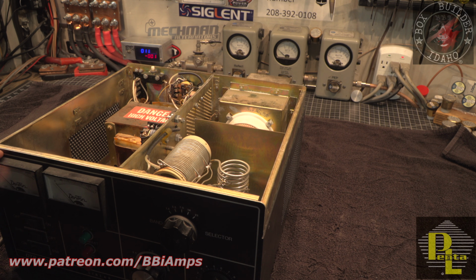Our meter says we're at 0. I have always been a proponent of, when the meter's at 0, still don't trust it, because the meter could be off by a couple hundred volts. There could be a little bit of stray voltage in there.